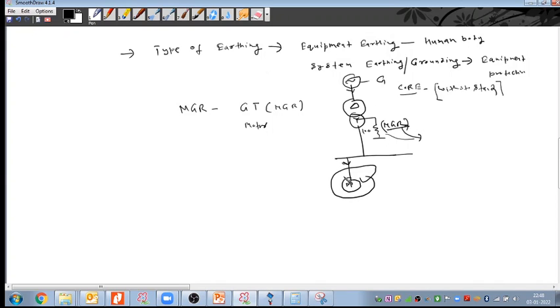Okay. That means the NGR value could be different depending on how you calculate the value of resistance. They may have different values based on how much current they want to limit. And this may also depend upon the CT ratio connected to the neutral, right? For the protection system, do not go on the CT ratio first, because the CT I will decide based on how much current I want. First I have to put the NGR, then we will go on the CT. So the NGR value depends on how much current I want to limit.